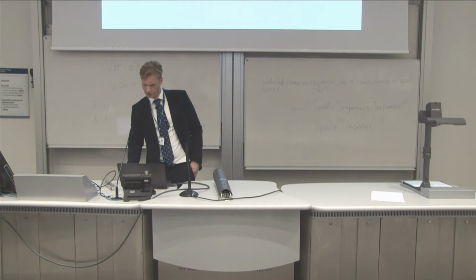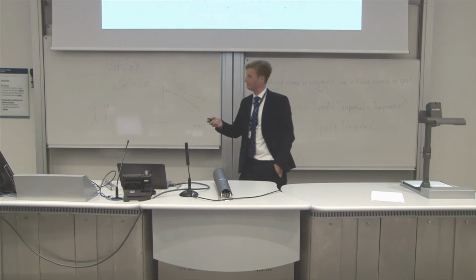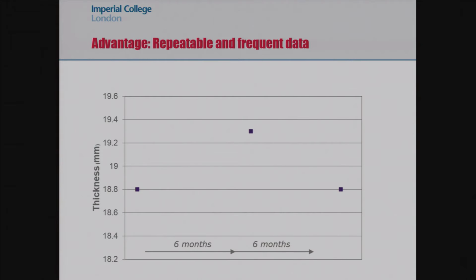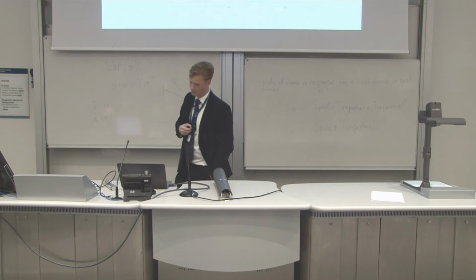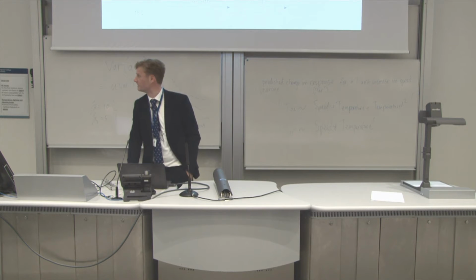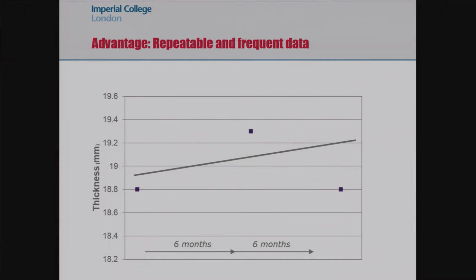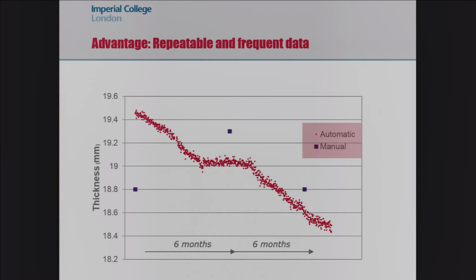And just to demonstrate the advantage over the status quo at the time: if you do manual measurements, usually you have to shut down the plant, or just getting there was difficult. So the most frequently you could do this was at about six-monthly intervals or so. Also, if an operator goes out there, there are all sorts of coupling errors associated. Are they really in the same spot? Are they coupling the probe and setting it up in the same way? Usually there's an uncertainty of about half a millimeter. So if you want to look at trends, whether it is going downwards or upwards, it's a bit difficult to tell. But if you look at automatically monitored data, then you can clearly see you get a lot more information.